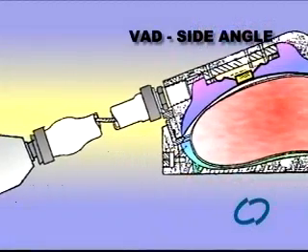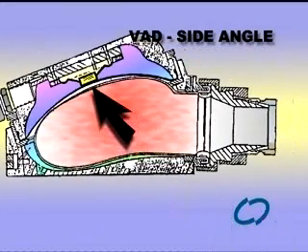The VAD blood pump consists of a smooth, seamless pumping sack made of Thoralon, Thoratec's proprietary polyurethane material, enclosed in a rigid poly-sulfone housing. Inside the VAD, two mechanical tilting disc valves maintain unidirectional flow. On one side of the housing is an electric Hall-Effect fill switch, which senses when the VAD is full and signals the driver to initiate the next eject cycle.